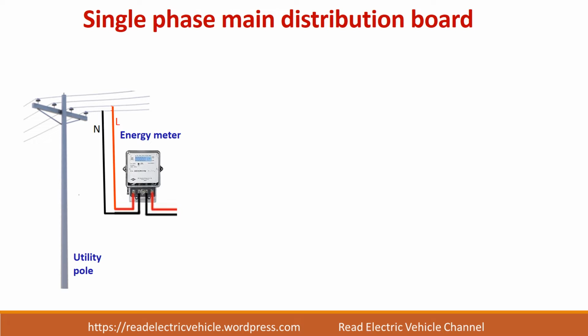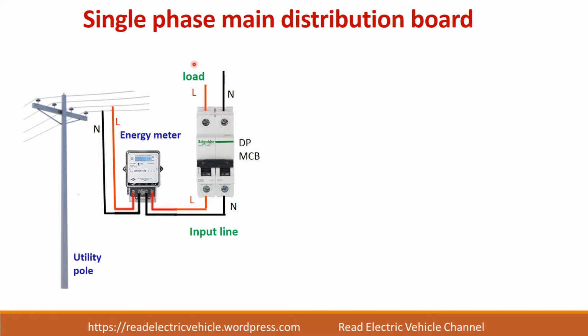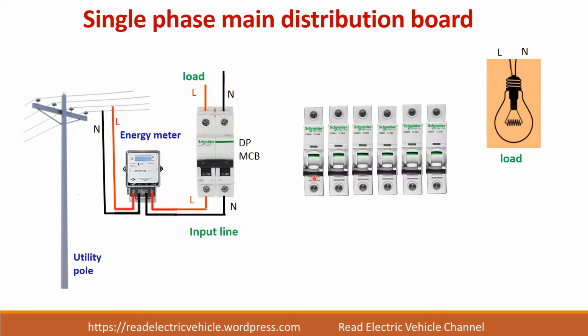The output of the energy meter should be connected to the dual pole MCB. To the bottom line we are connecting the output of the energy meter, and the other end of the MCB will be connected to the load. Load also has two terminals, line and neutral. In our home there will be many loads. Each load can be connected through a single pole MCB. So this is a single pole MCB. We have to connect the load through this switch, so that whenever there is a fault current, this will trip and isolate that particular load.